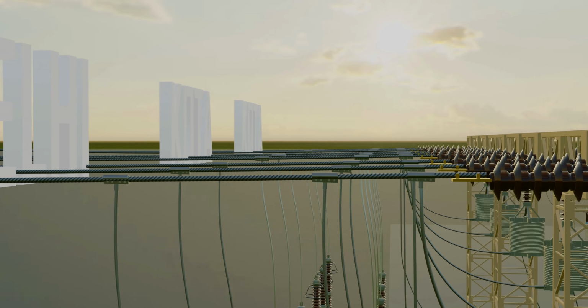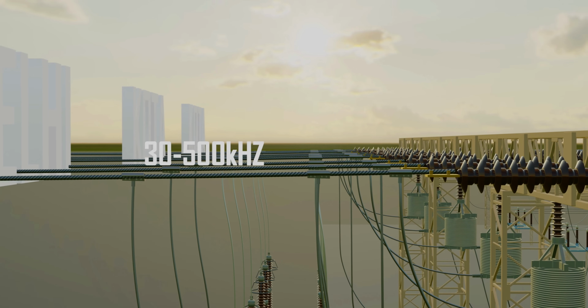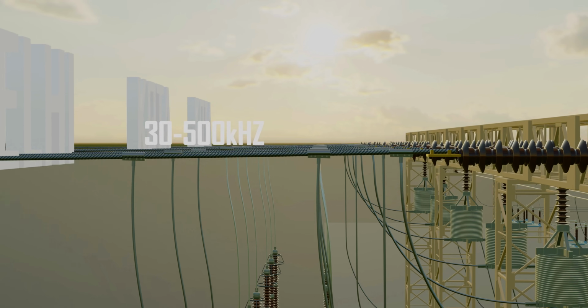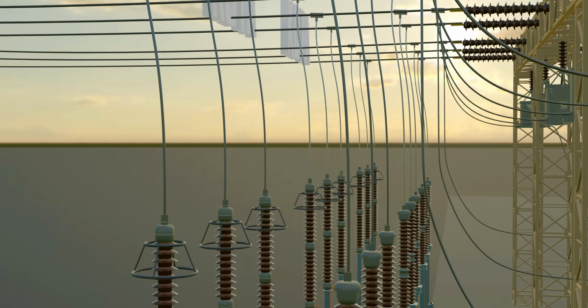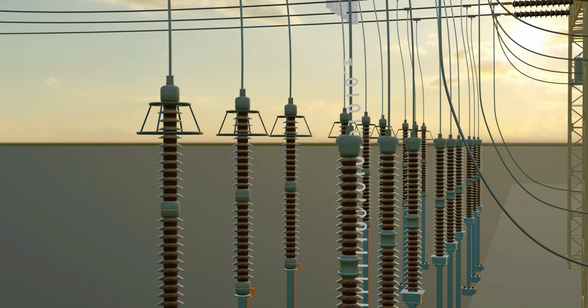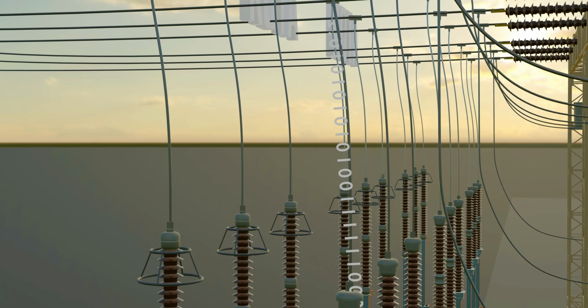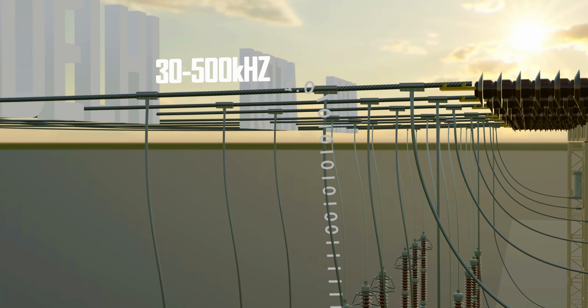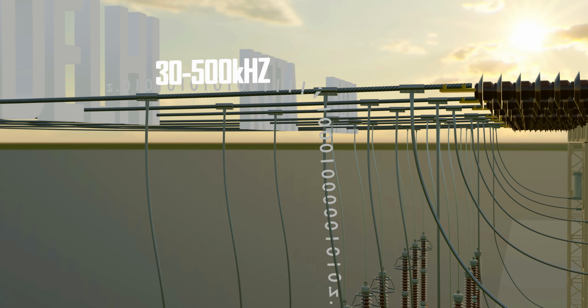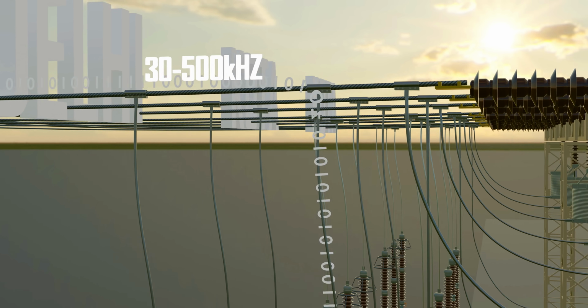Power transmission lines typically use frequencies between 30 kHz and 500 kHz, so that communication speed is much slower compared to mobile networks. The CVT plays a key role in this communication process. It helps inject and receive signals within the transmission line. These signals are high frequency, while household electricity operates at just 50 Hz.